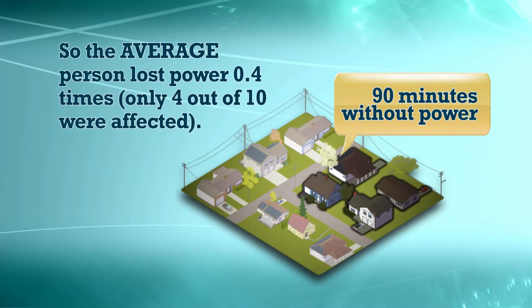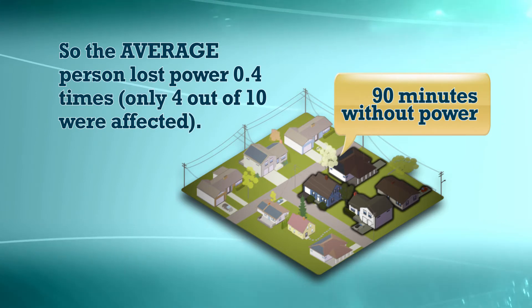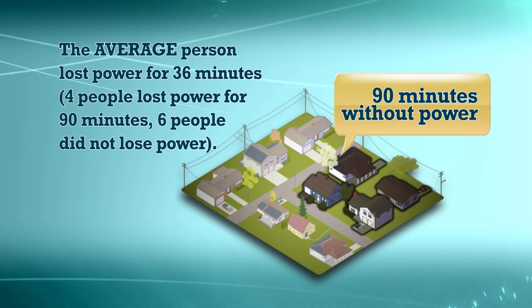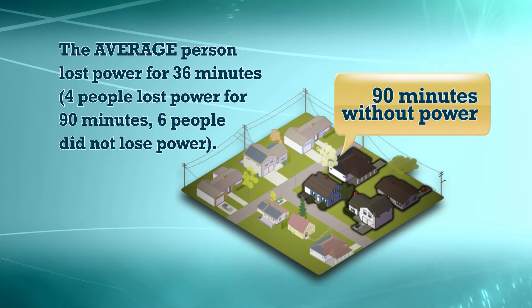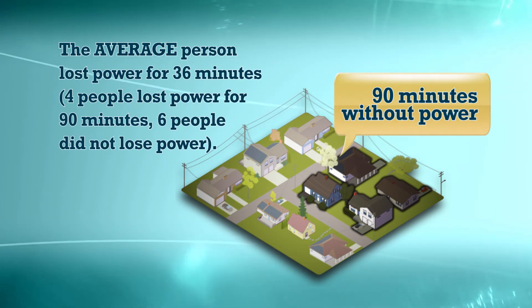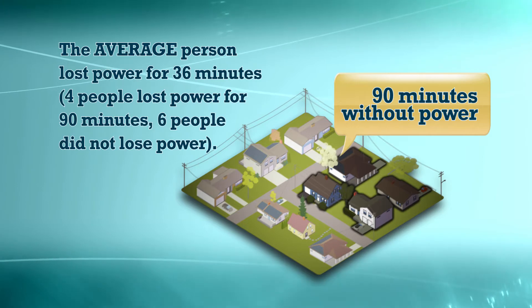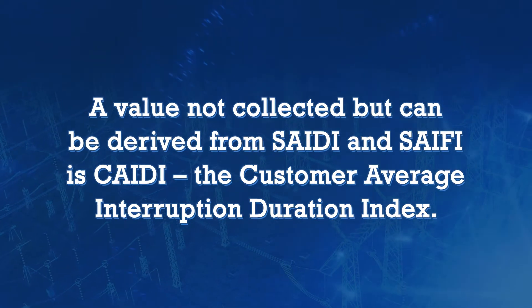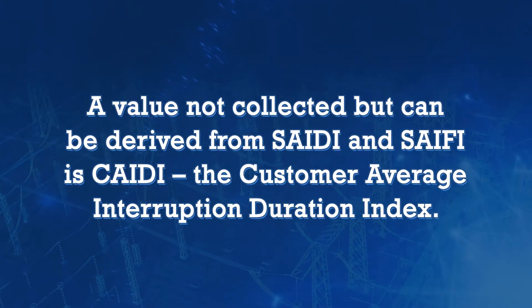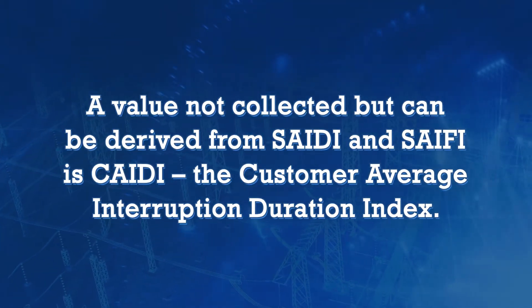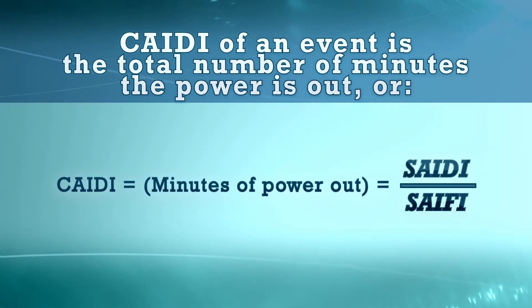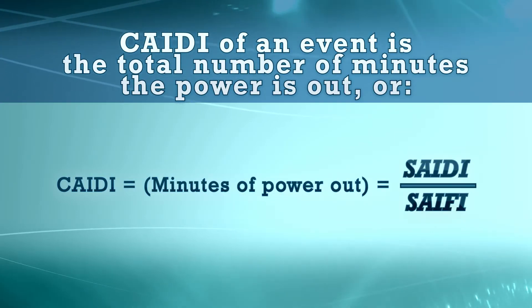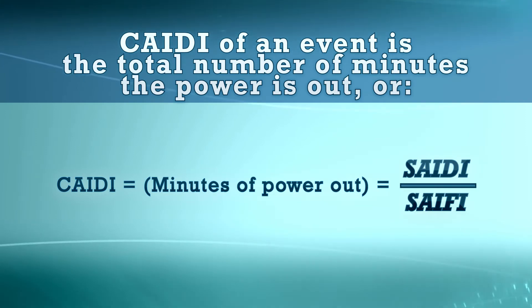So the average person lost power 0.4 times — only four out of ten were affected. The average person lost power for 36 minutes. Four people lost power for 90 minutes; six people did not lose power. A value not collected but can be derived from SAIDI and SAIFI is CAIDI, the Customer Average Interruption Duration Index. The CAIDI of an event is the total number of minutes the power is out, but can also be calculated by SAIDI divided by SAIFI.